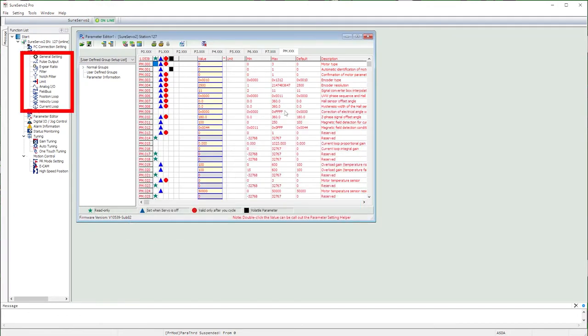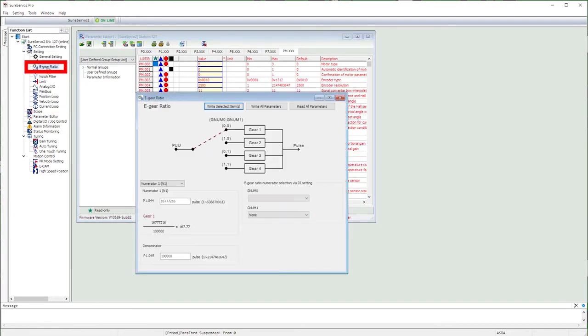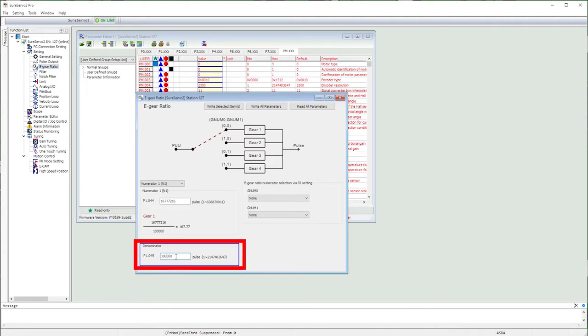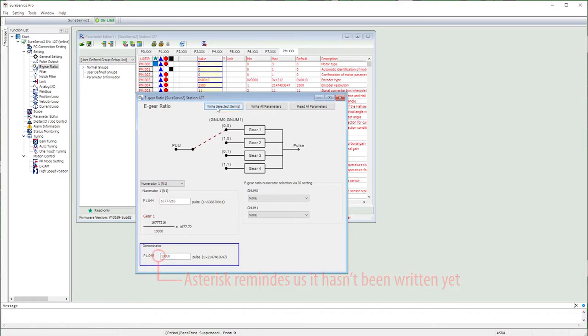We don't need to fool with any of this, but let's modify the electronic gearing like we did in the quick start video with 10,000 pulses per revolution. That's more than enough for what we are doing. This is important. Setting it here doesn't get it to the drive until you actually write it out.